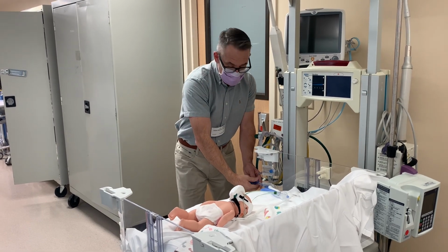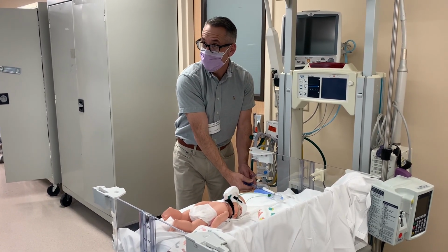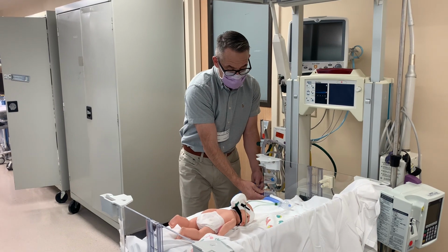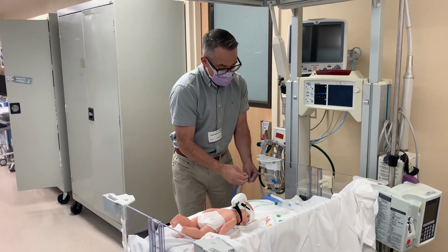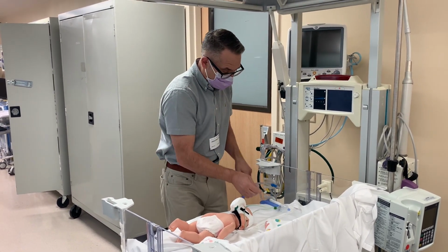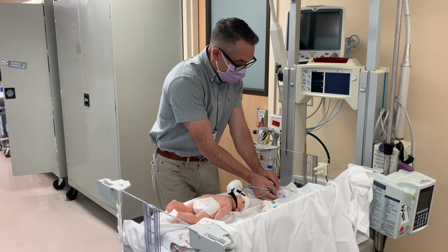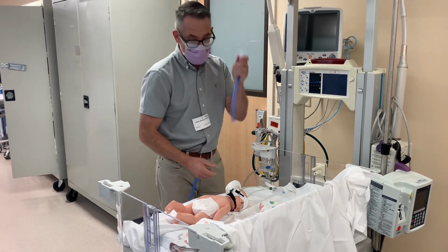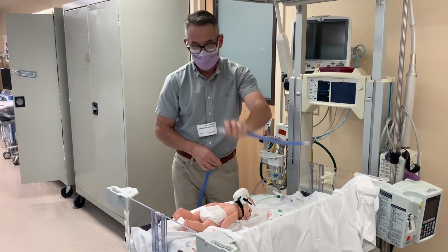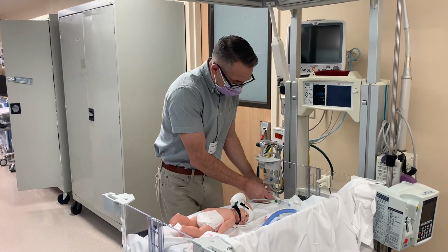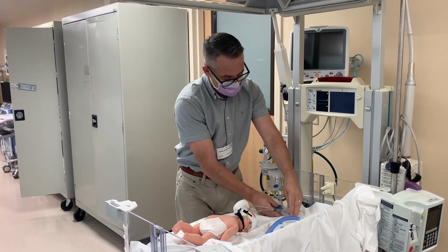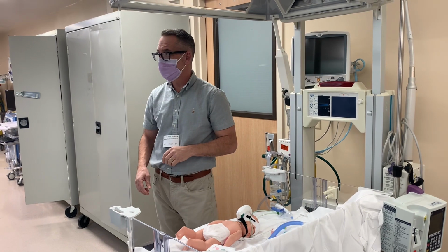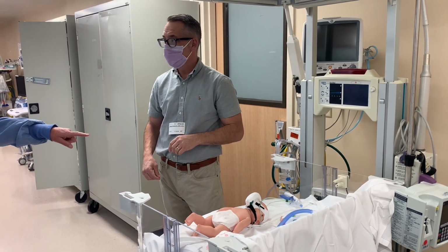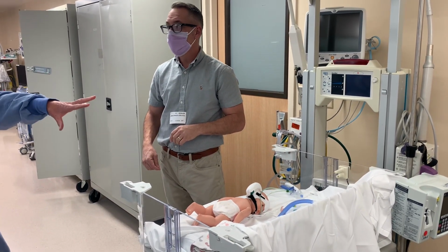So you've got to make sure it's seated all the way down and you don't see any other teal. But the fastest and easiest way to eliminate any ambient air that's happening outside is just take this extension unit, which comes in every single kit, get rid of it, and plug this in like so. So it's always going to be more stable temperature inside the isolette. Always.